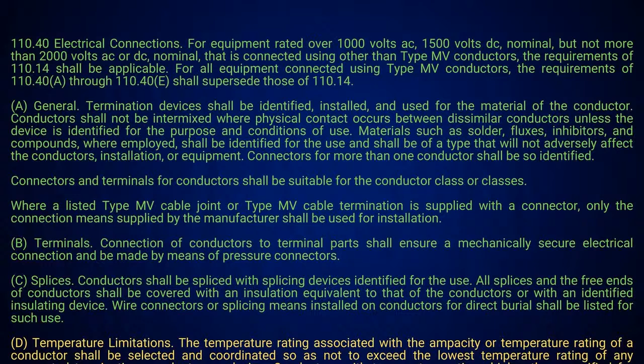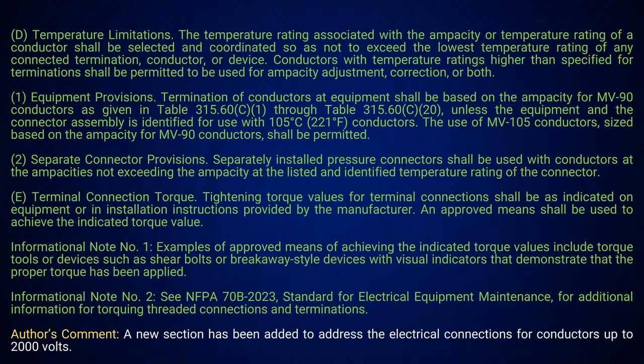I mean, there are some little differences, but if I'm looking at temperature limitations here, the last sentence says: conductors with temperature ratings higher than specified for termination shall be permitted to be used for ampacity adjustment, correction, or both. Right. See what I'm saying? So when you get into high voltage, you've got different temperatures on there, so you'd be able to use a higher temperature. Okay. Well, we're not only getting into high voltage, we're getting into high voltage live. Mm-hmm. And that, folks, gets you through Article 110. And next week we'll be looking at Article 120. That's going to kick back to where all the information that was contained in Article 220 has now been moved to Article 120. All right.